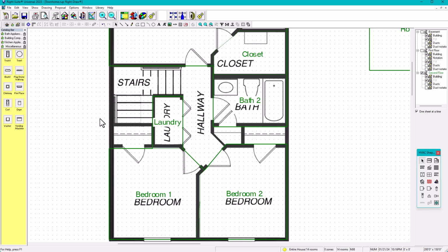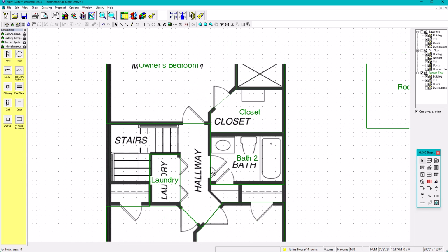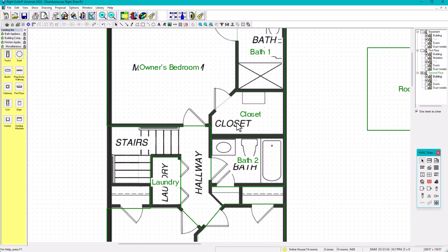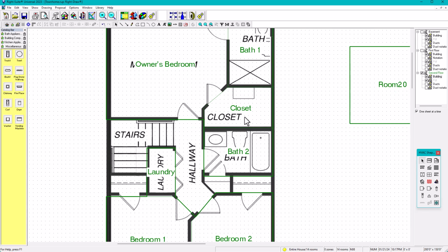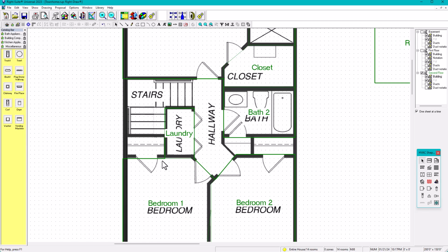Okay. So now in here, we forgot about the closets. So we should put closet 1, closet 2. However, this closet is small, and usually from my experience we put registers on the closets of the owner's bedroom because it's big. And also sometimes in big mansions they have the closet for her, the closet for him. They have their own closets, right? So we want to put our registers right there. But when it's a single person's bedroom, and we have a small closet, usually we don't put anything. So sometimes we just basically just put an undercut in here. Okay, so that's the reason we're not gonna put a room. We're just gonna add it to the bedroom.